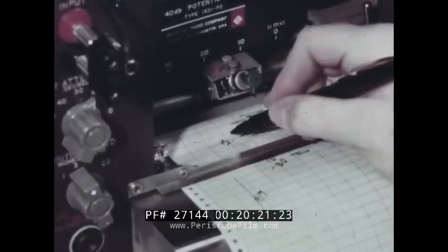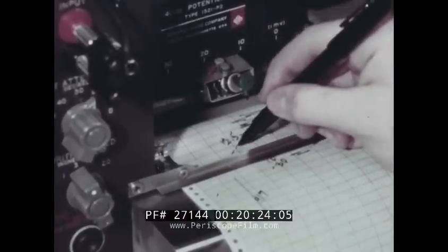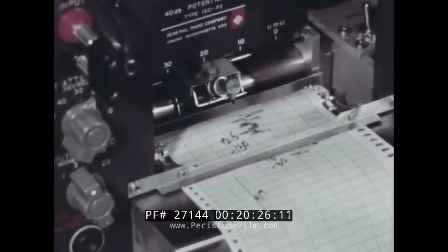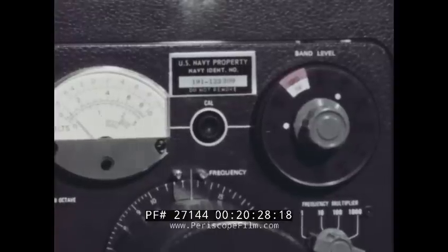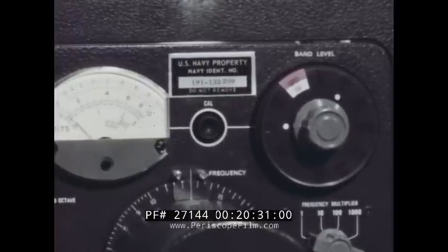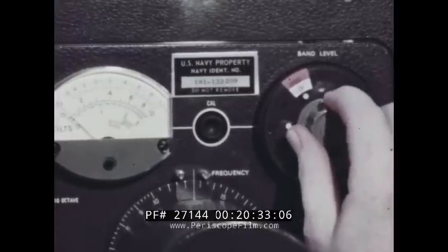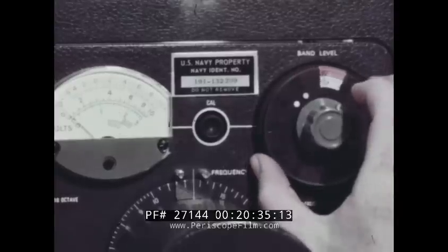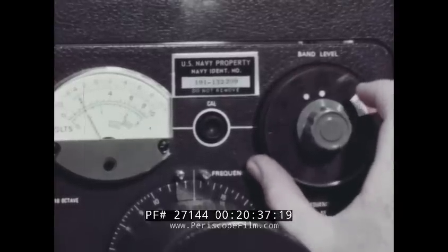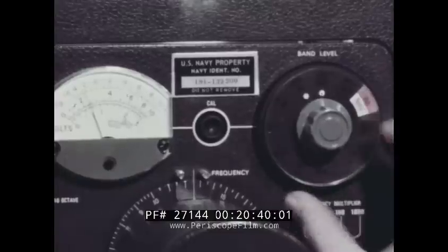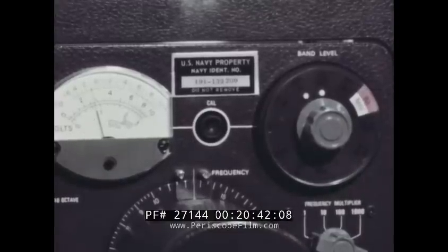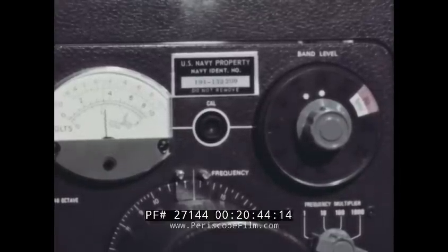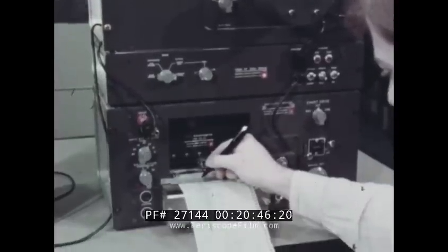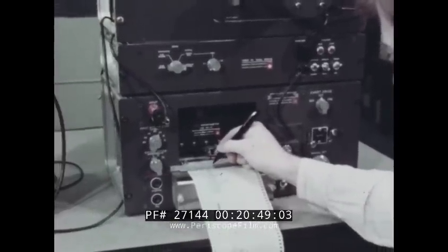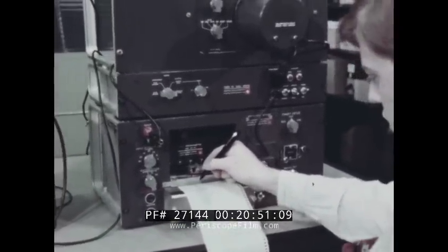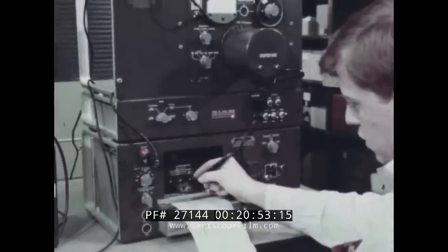But what happens in the case of an off-scale reading? If you remember what we said earlier about attenuator settings with this combination of equipment, you'll know the solution is to adjust the dials on the analyzer. Turn till you get an on-scale reading. You have changed the level of the signal being fed to the recorder by 40 dB. Be sure to write this change on the chart. You must remember to write down every change in attenuator setting, or your data will be worthless.